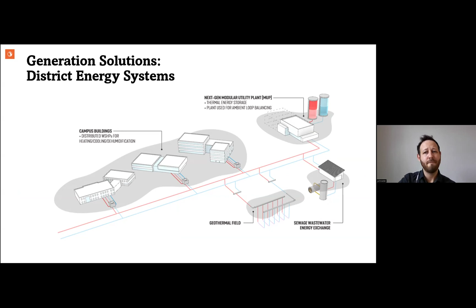I wanted to quickly speak about some of the differences between distribution systems. So a two-pipe 'ambient loop' — I use that in quotations because sometimes we might change the temperature slightly from just beyond ambient — but really it's a two-pipe system running water at fairly low temperatures, quite low compared to steam systems, and then elevating those temperatures at the buildings.